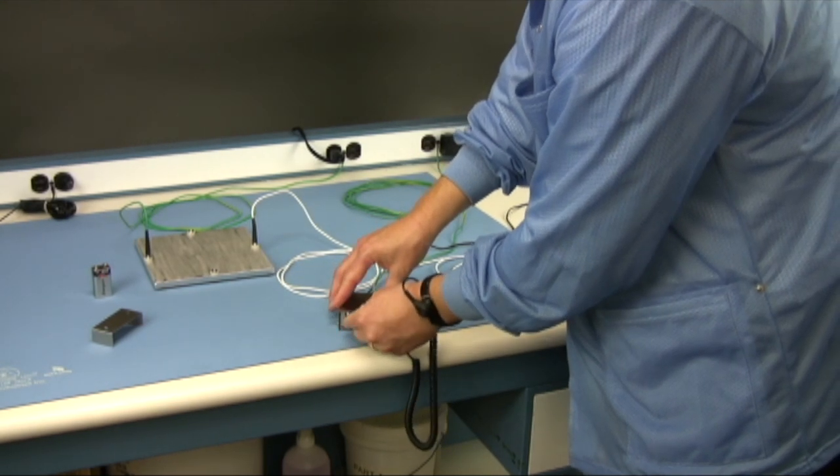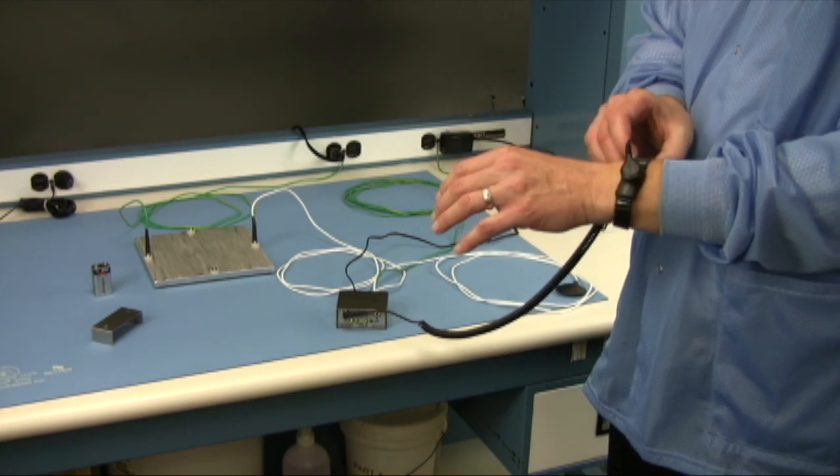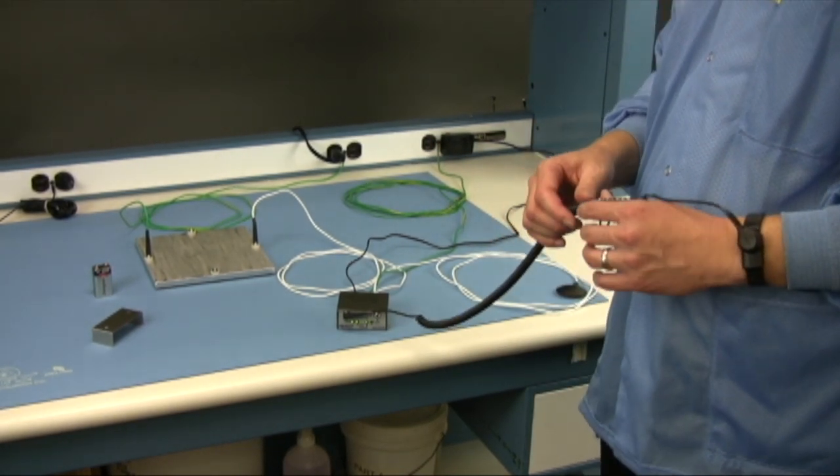The operator and supervisor circuits work with a dual wire wrist strap such as the Desco MagSnap 360. Both circuits monitor for the path to ground and voltage on the body in excess of plus or minus 3 volts.